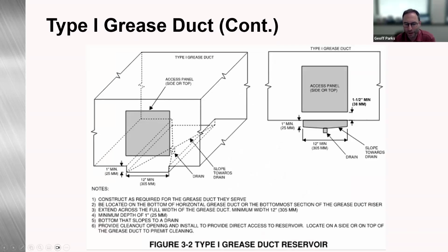And then also new to that document, that's going to be in the 2026 edition, we've added Figure 3-2, Type 1 grease duct reservoir. So this provides a detail of that reservoir, and then also some of the requirements based on code. It is required for the grease duct they serve, located on the bottom of horizontal grease duct or the bottommost section of the grease duct riser, must extend across the full width of the grease duct, minimum 12 inches wide, have a minimum depth of 1 inch, and a bottom that slopes to the drain. And then you must provide a clean out directly at the access to the reservoir, either on the side or the top of the duct to permit cleaning. So this is a new detail that we have.